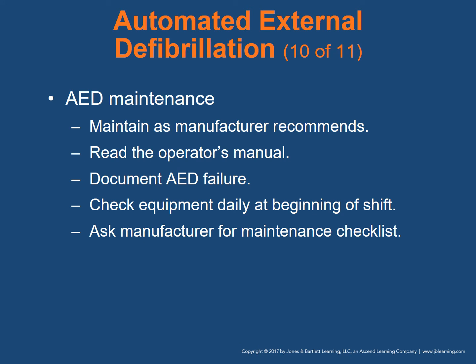We must maintain our AEDs just like every other piece of equipment. Understand how it fails. Understand that most of the time when an AED fails, it's because we didn't correct it. We didn't fix it the way that it needed to be. We didn't check the batteries. We don't have the right pads. All things that we can do and we can ensure are being met.